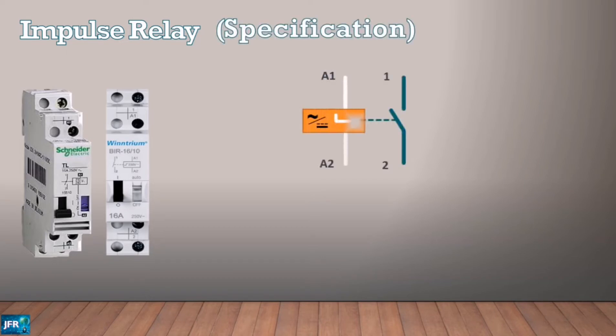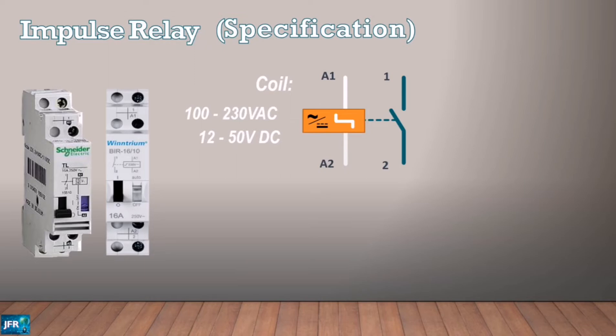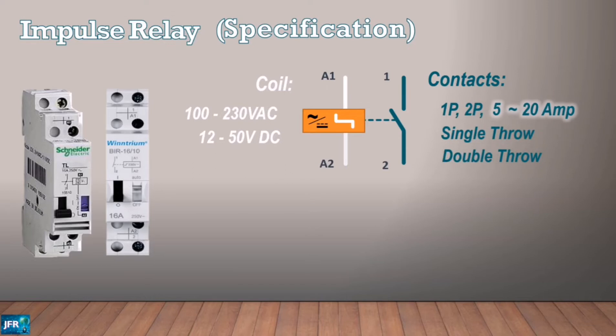For specifications, relay coils can be from 100 to 230 volts alternating current, or 12 to 50 volts direct current power source. Relay contacts can be a single pole or two poles, rated from 5 to 20 amperes. Depending on your application, there are a variety of specifications available in the market.